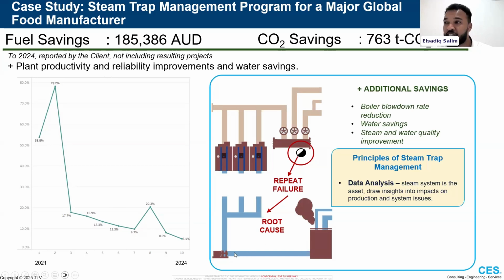They found there were some major issues there. They did an upgrade and that resulted in massive water savings as well as steam and water quality improvement on site. So something as small as a steam trap can have wider implications—a key point that you only find if you do consistent, repeated testing and inspection of the steam traps.